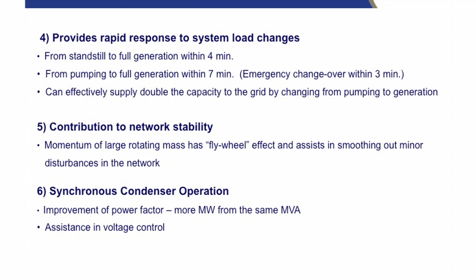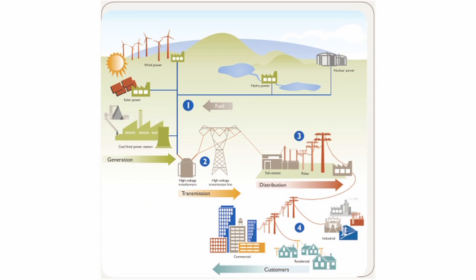And if you were pumping and you suddenly have to stop pumping and start generating, we can do it within 7 minutes. And by doing that, you actually double the capacity of a pump storage to the grid. Because while you're pumping, say you've got 1,000 megawatt pump storage, you consume 1,000 megawatt. If you stop pumping, immediately you regain that 1,000 megawatt, and then if you start generating, you add another 1,000 to the grid.